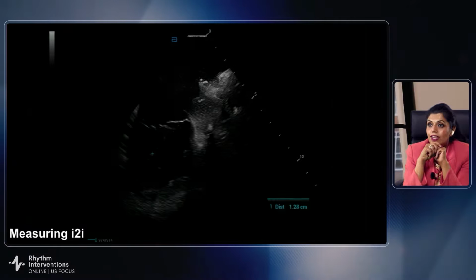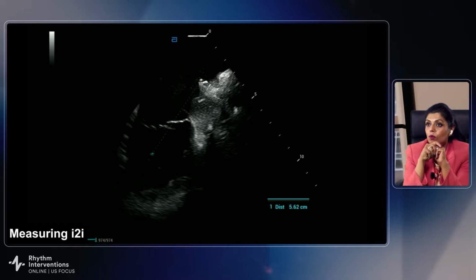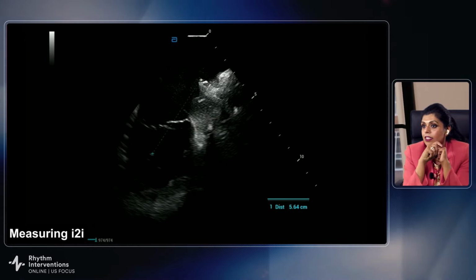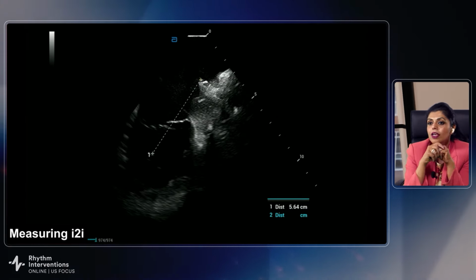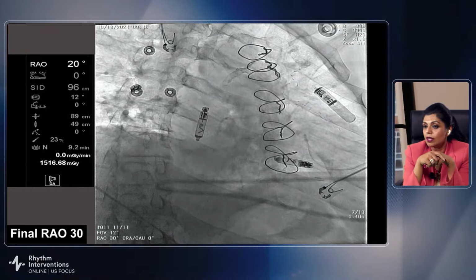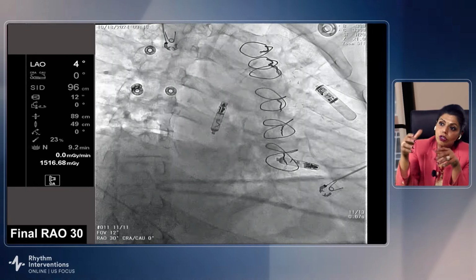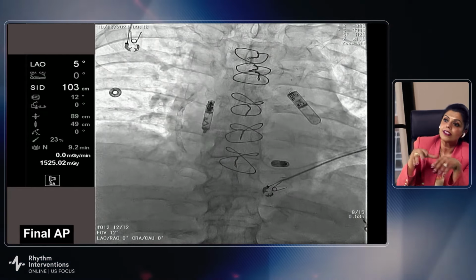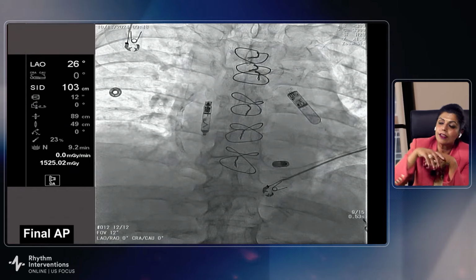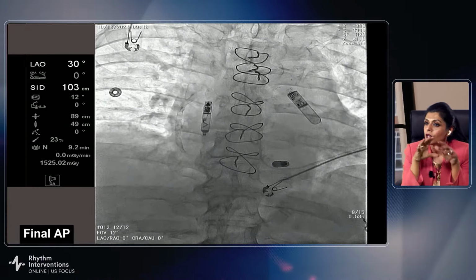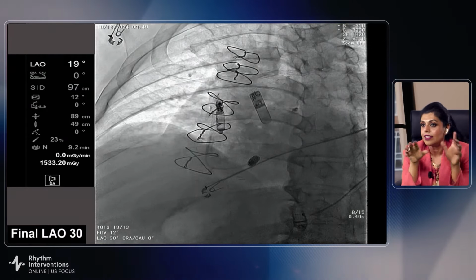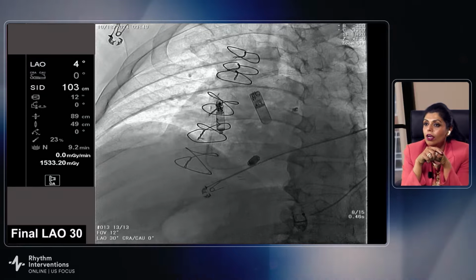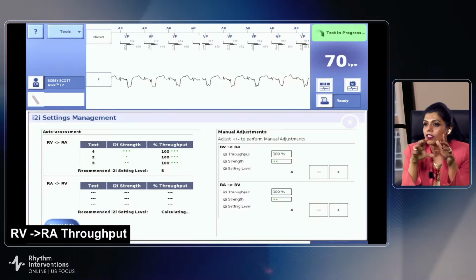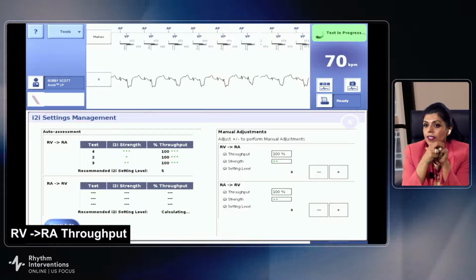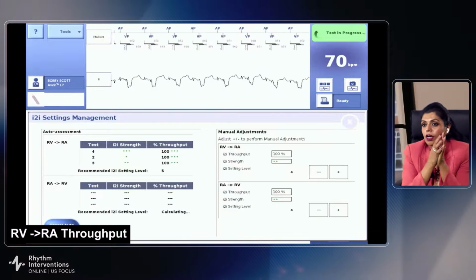So here you can see we just released the device, two nice stable devices, and we're measuring the implant-to-implant distance. The distance is about 56 millimeters here. Anything under 70 millimeters is adequate. And you're also looking at the orientation of the two devices relative to each other, looking for less than a 40-degree angle. And that's a little bit harder to adjust. I think distance is a little bit easier to make happen, whereas the orientation of the device is a little bit harder to adjust.